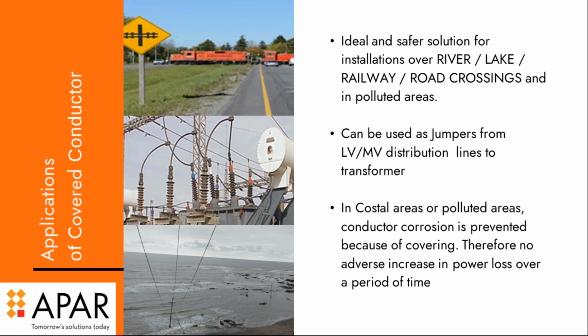It is also used in coastal areas and highly polluted, corrosive industrial areas with a lot of industries. These are excellent applications for covered conductors, because in the salty environment there is no effect on the conductor inside the insulation. It is a watertight conductor, so it can serve its whole life of 30 to 50 years without any damage from corrosion, saltiness of water, or pollution in the network areas.